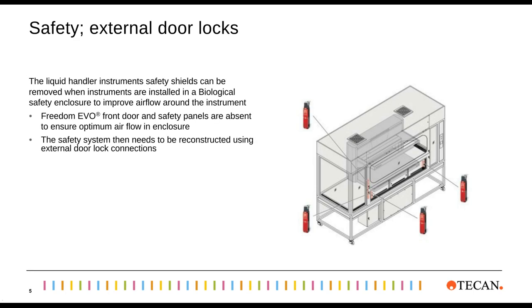For many of the instruments, we'll actually take off our safety doors when we install these into a hood. The reason for that is to allow good airflow within the instrument. And we'll often end up replacing the safety interlocks on our instrument with safety interlocks on the actual hood and enclosure itself, and wire those into the operating system of the instrument. So you maintain that safety lock system, but it's changed from being directly on the instrument to being part of the actual enclosure itself. And again, this is an important aspect of the design of the hood systems that you'll need to purchase.